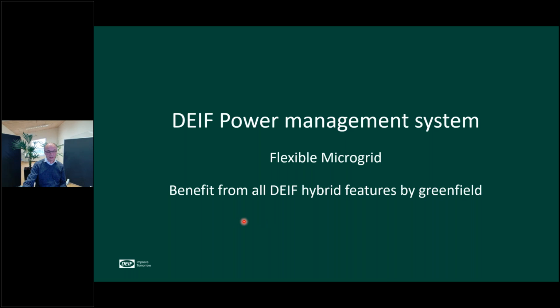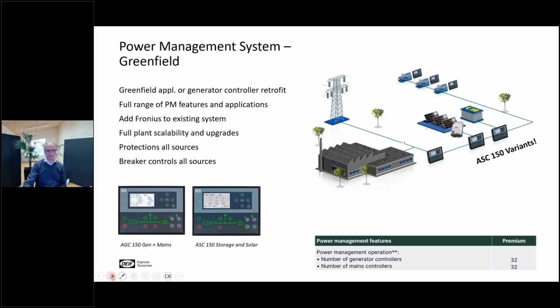The DEIF power management system that you maybe know from before is a flexible microgrid system, again with all the features from the power management. So here it's a new system. If you have the generator controller retrofit possibility, you can use this system as well, and then you get the full power management features: priority exchange, safety functions, load dependent start and stop functions, and spinning reserves. So here again, it's easy to add Fronius to the system, because the controller is part of the integrated system.